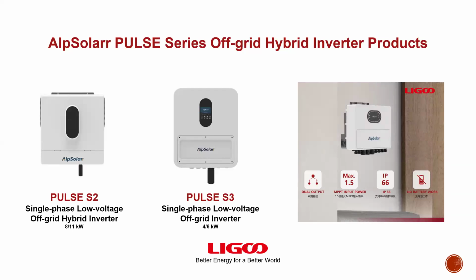The first selling point and feature of this Pulse S3 inverter, our 6 kilowatt inverter, is that it is rated IP66. It has an ingress protection of 66, which makes it suitable for outdoor installation as it is properly protected against dust and water. We know that because of some fire incidents that have been directly or indirectly associated with inverter systems, some homeowners, as most installers can agree with me, are not comfortable putting their system inside their house. So they are looking for a system that can stay outside while they are inside.